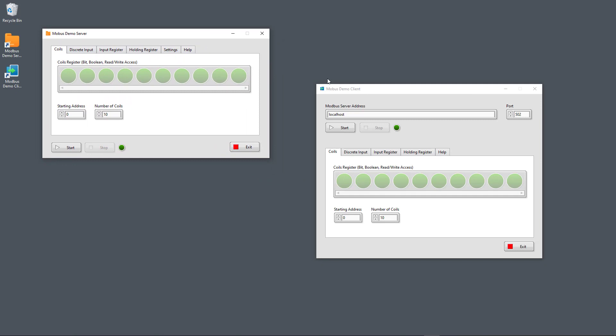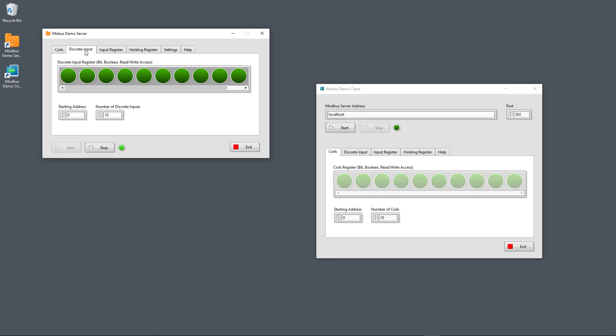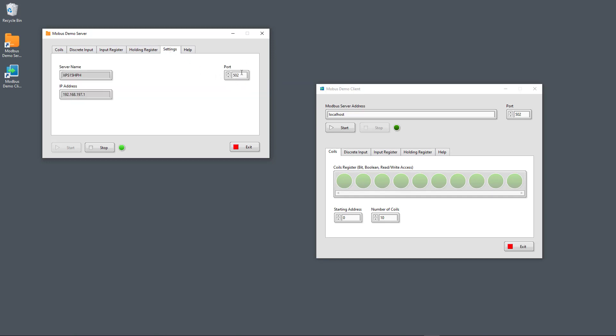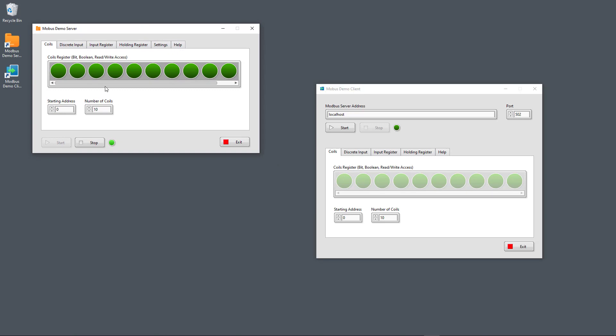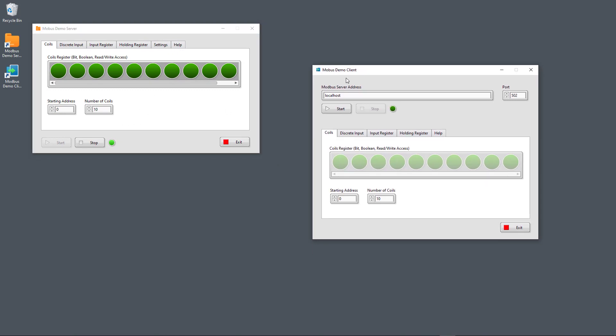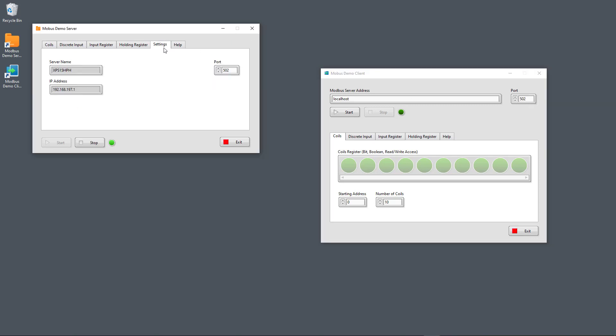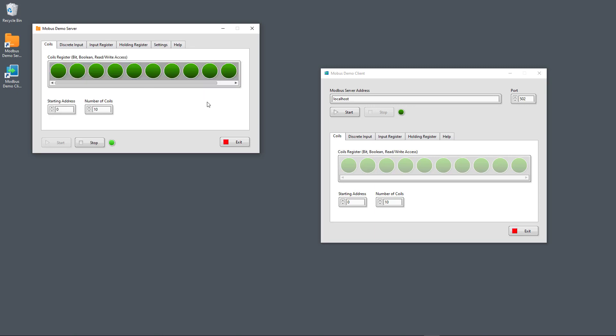Now I have the Modbus Demo Server and the Modbus Demo Client open. To start the Modbus Demo Server, I just click here on the Start button. Now we have the coils register here, the discrete input register here, the input register, and the holding register. You can also specify the port — the default port is 502. Now the Modbus server is up and running. To start the Modbus Demo Client, you need to specify the Modbus server address — typically an IP address, but since both are on the same computer, I just type localhost — and make sure the port matches the server, then click Start.